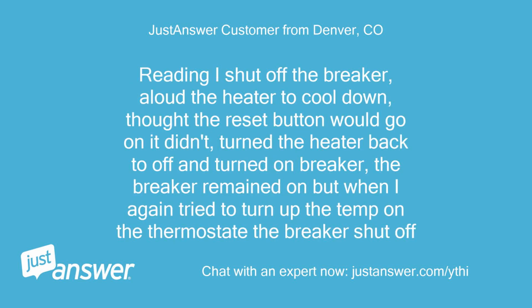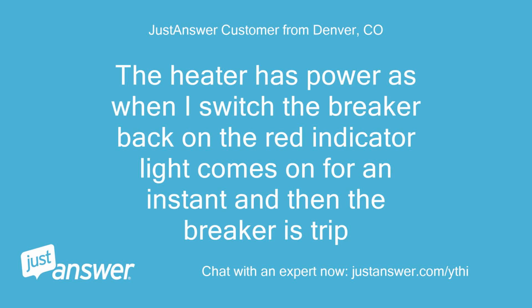I shut off the breaker, allowed the heater to cool down, thought the reset button would go on, it didn't, turned the heater back to off and turned on the breaker. The breaker remained on, but when I again tried to turn up the temp on the thermostat, the breaker shut off. The heater has power, as when I switch the breaker back on, the red indicator light comes on for an instant and then the breaker is tripped.